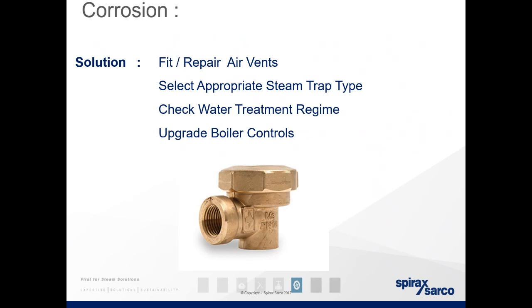Yes, there's one question. The question is, how could you identify corrosion on boilers? It is relatively easy. When you inspect your traps on your routine inspections, you'll see more particulates than you have seen before in the strainers. You'll see the inside of a pipe become thinner. One of the inspections you should do on a boiler is the wall thickness, to tell the lifetime left on that boiler. That will also highlight any excessive corrosion or erosion inside there. Same on a steam pipe. Wall thickness tests on pipes are essential to be able to maintain the maximum allowable pressure in the system.